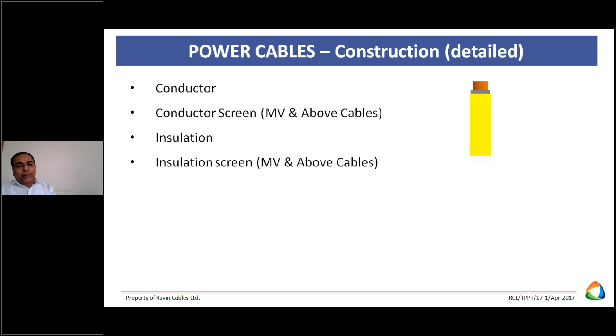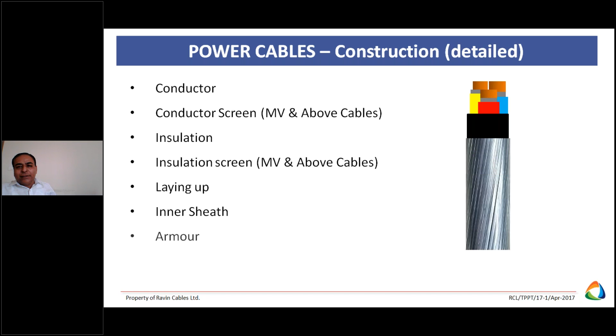Now see the construction part. Conductor screen, insulation screen, then copper tape, then red, yellow, blue identified cores are there, put together to protect with mechanical protection inner sheath. Again, armor for mechanical protection as well as electrical protection at the time of short circuit. Then to protect the armor, outer sheath. Again, the sheath materials vary as per the site requirement.